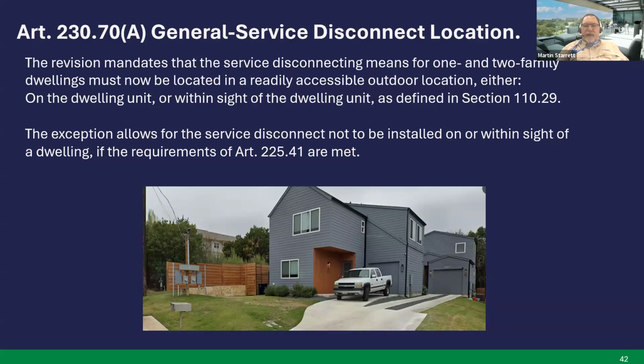But those of you that have been doing installations here in Austin, you said, well, we've always been putting it on the outside. That's because of our local technical amendment. But since now they're requiring it on the outside, there's no need to say that anymore. Now, there's an exception that allows for the service disconnect not to be installed on or within sight of the dwelling if the requirements of Article 225.41 are met. We just previously looked at that. That's for the emergency disconnect.